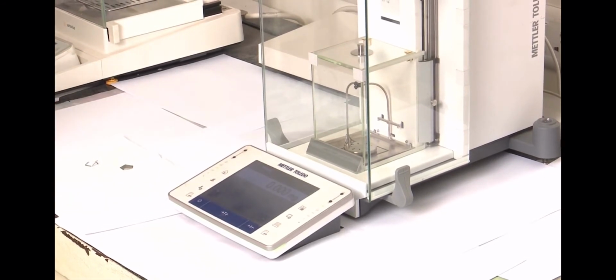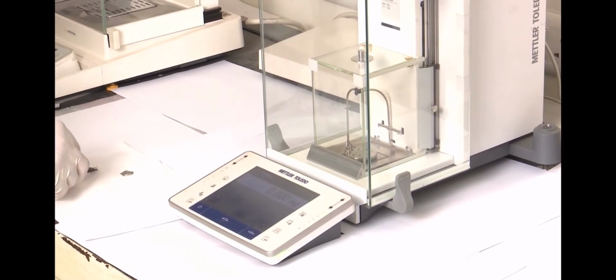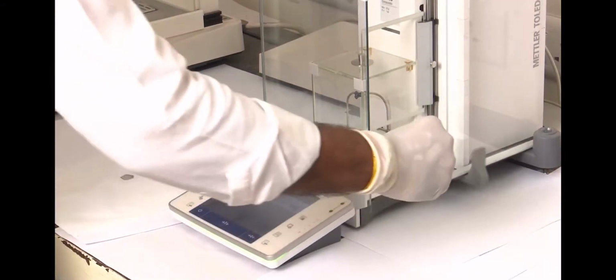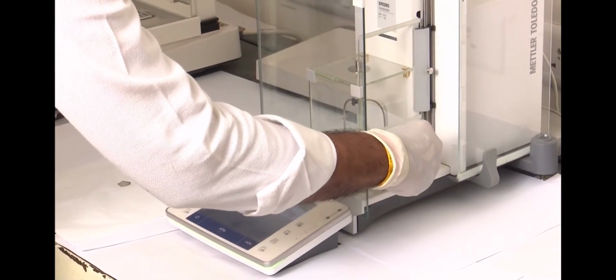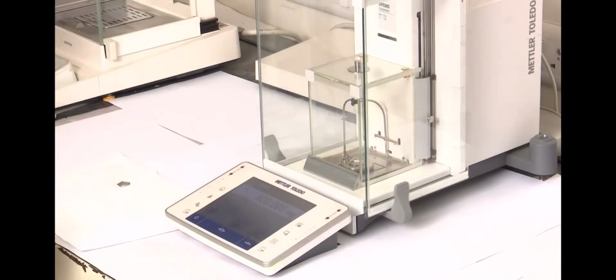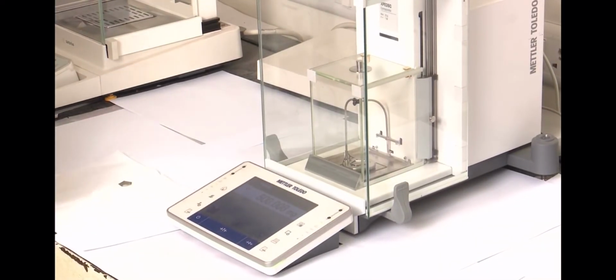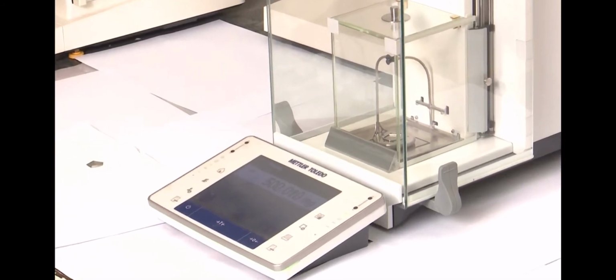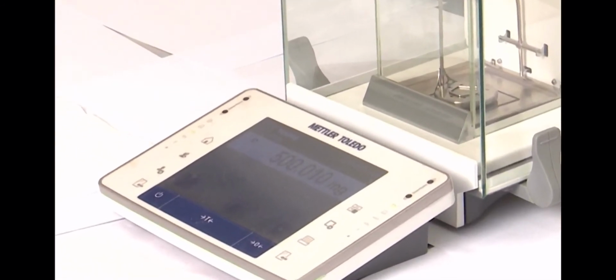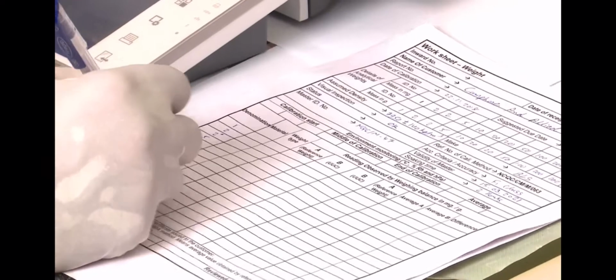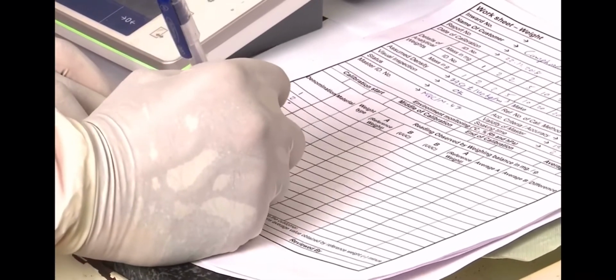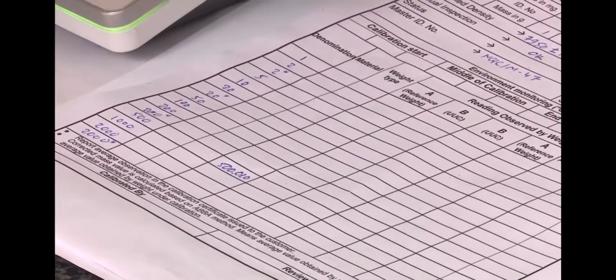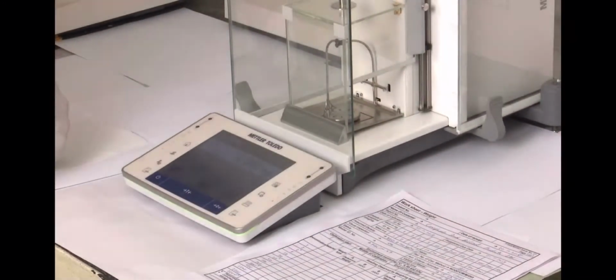Now I will perform weight calibration by ABBA method. Put reference standard weight on the center of pan of the balance. Close the door and allow it to stabilize. Note down the reading shown by weighing balance as A. Take out the reference standard weight and allow the balance to stabilize at 0.